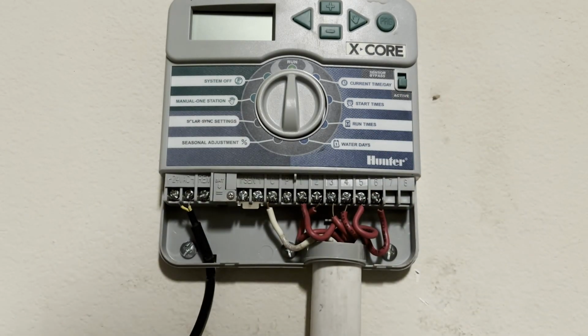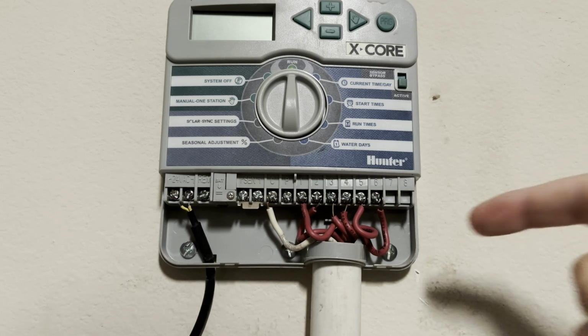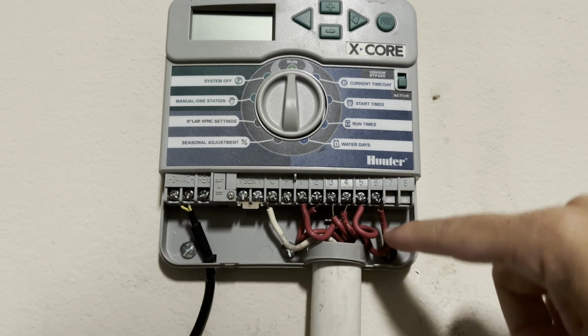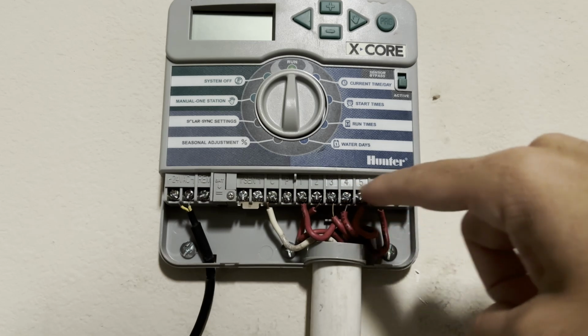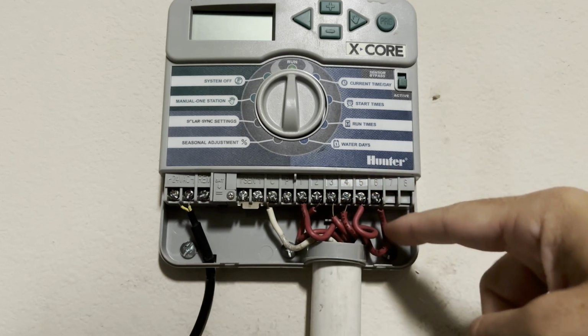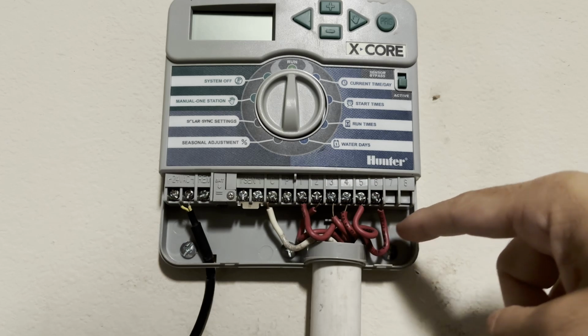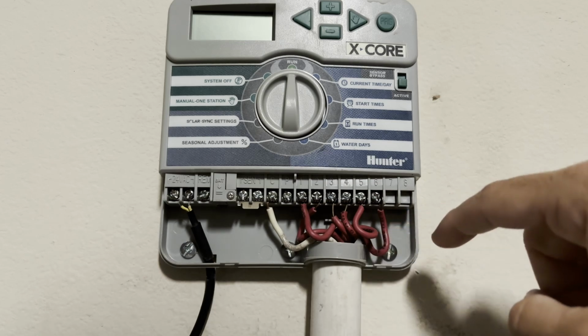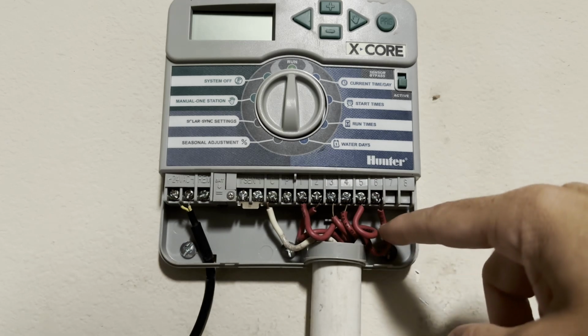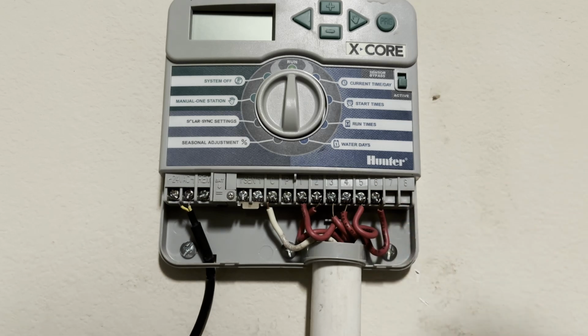The most important part of this process is making sure we wire the new control panel the same way this one is wired. You'll definitely want to take a before photo so you always have that to reference back to. As we disconnect wires from each of these zones, we'll label each one with a small piece of tape so we don't have any mix-up when reconnecting to the new panel.